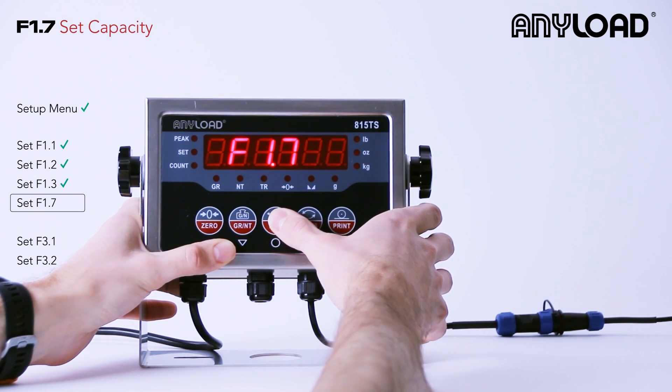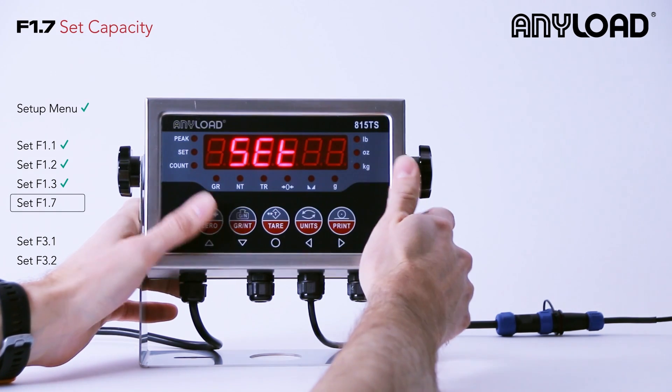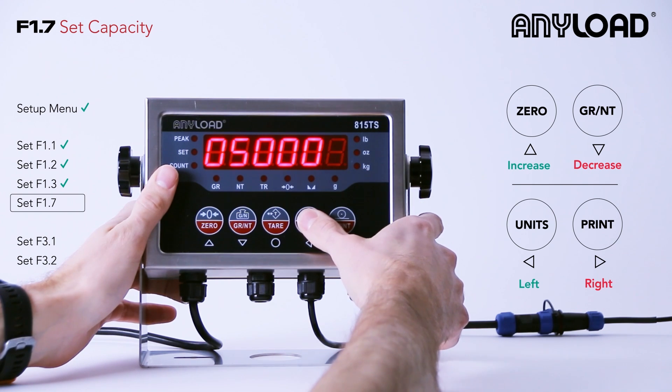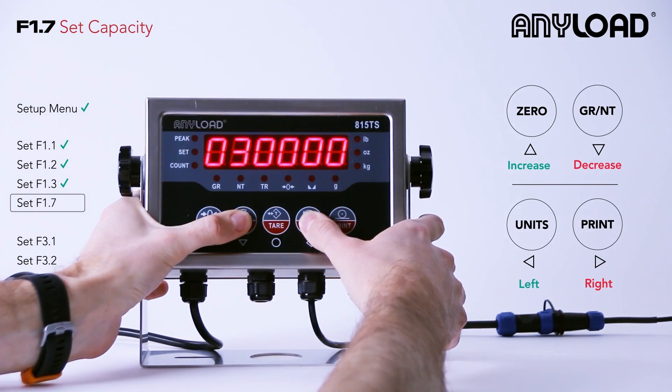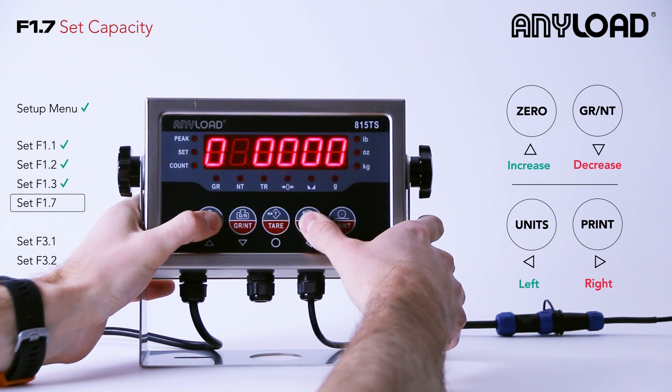F1.7 is our max capacity. I can navigate left or right using the units and print button, also known as left or right, and I can increase using zero and gross, also known as up and down. We're going to set ours to 50,000 pounds and press tare to enter.